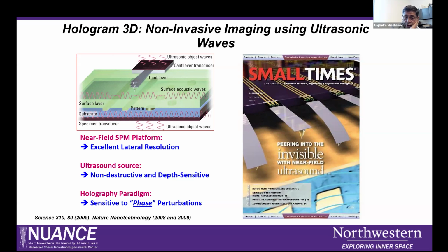Okay, so it's non-destructive. This is depth sensitive. You can tailor the frequency to go to a little higher depth and also adjust the resolution. It has excellent lateral resolution because we use a pretty sharp probe, so your surface resolution is mechanical resolution down to a few nanometers. And it's very sensitive to changes in the phase perturbations.